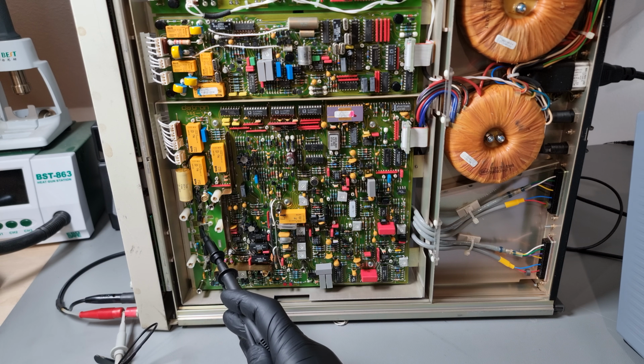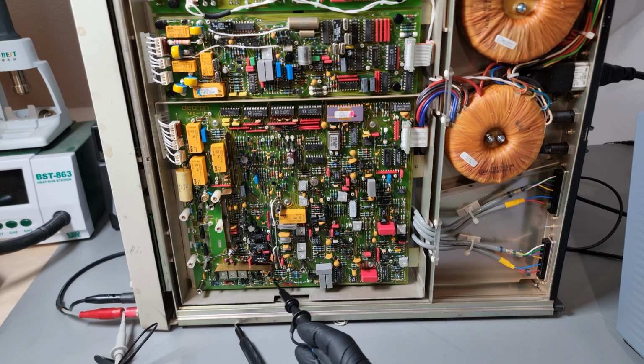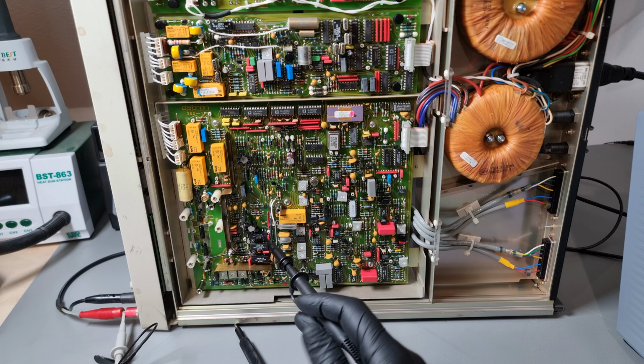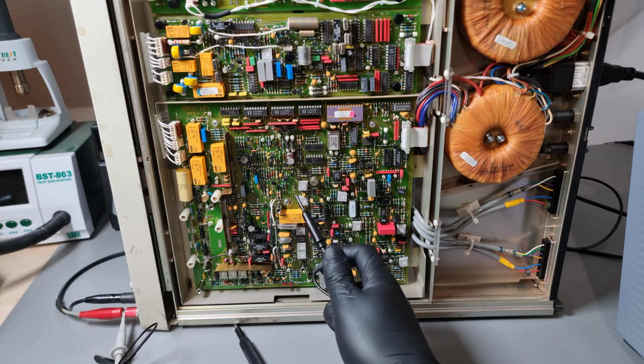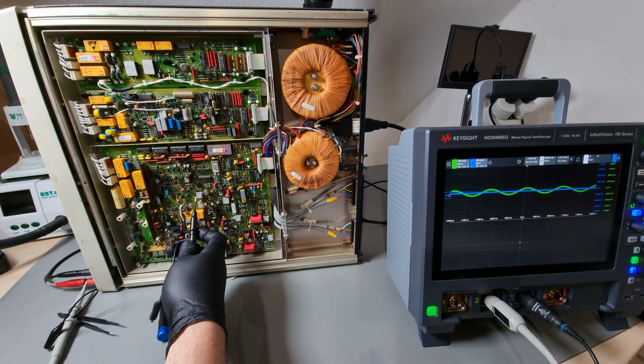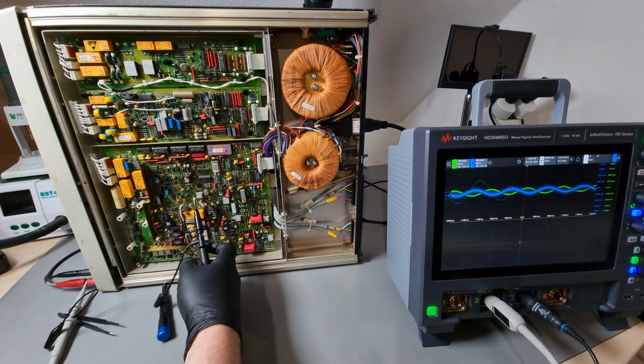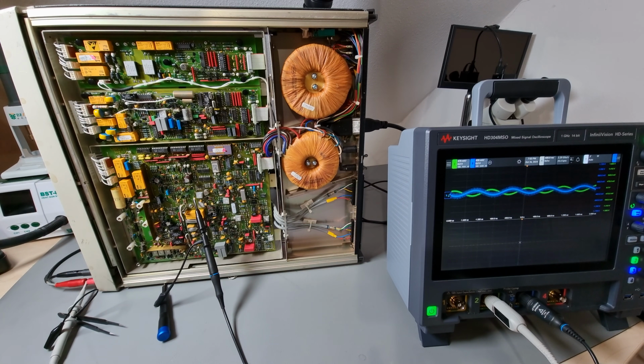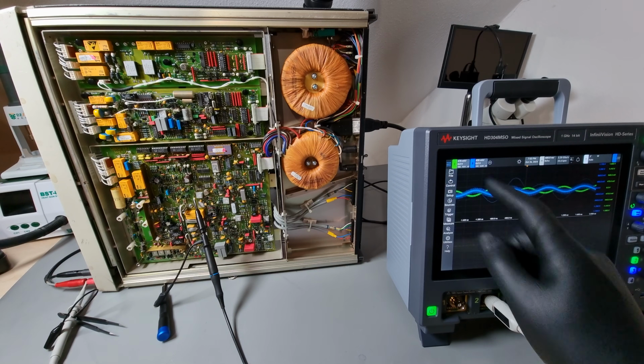All ranges from 100 mV to a kilovolt have to go through the attenuator, which is basically resistive for DC and low frequencies, with parallel capacitors taking over at higher frequencies. Nothing should be broken there unless there's been a huge catastrophic overload.